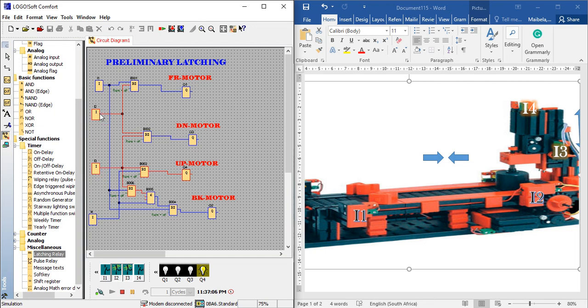Keep that in mind. I2 is still activated and it wants the downward motion to take place because the part is physically there at I2. Therefore, it will constantly demand the downward motion. The similar procedure or problem as we experienced with I4. So we're going to prevent it now. Imagine the process can take place smoothly. Then I3 would be able to let our system go up.